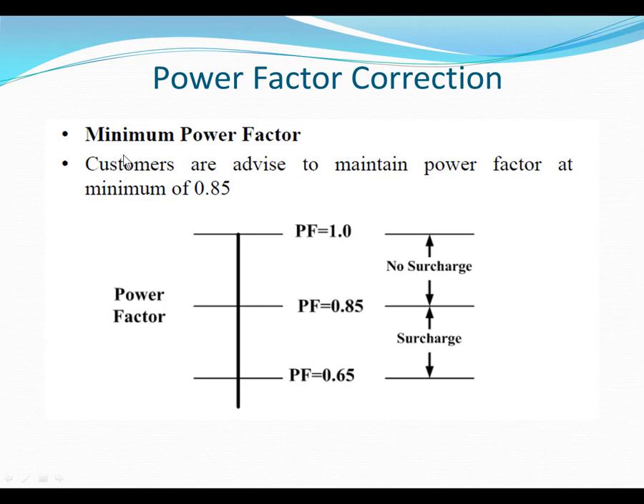In Malaysia, the electricity tariff is based on active energy or real power, and will be charged based on the measured real power in kilowatt-hours. It does not include any reactive power or KVARs. In order to recover the extra cost incurred in supplying the reactive energy required by the consumer, the utility imposes a surcharge.